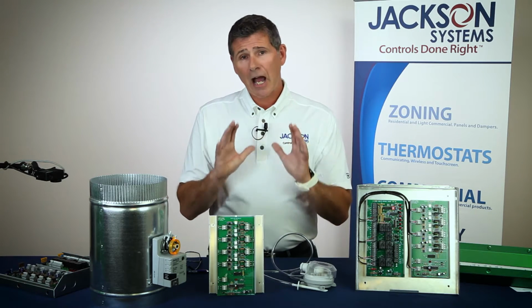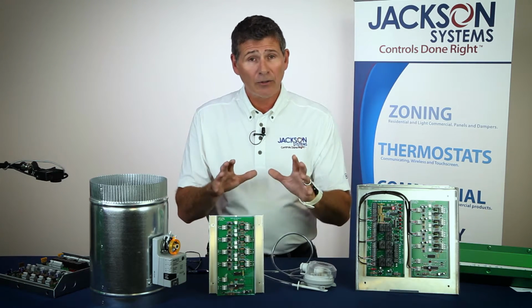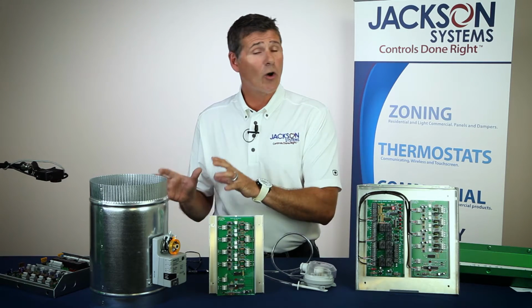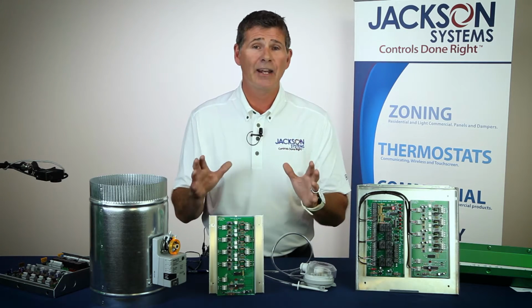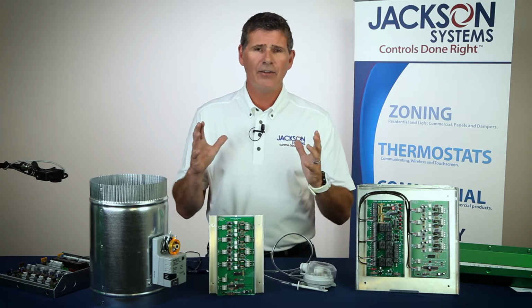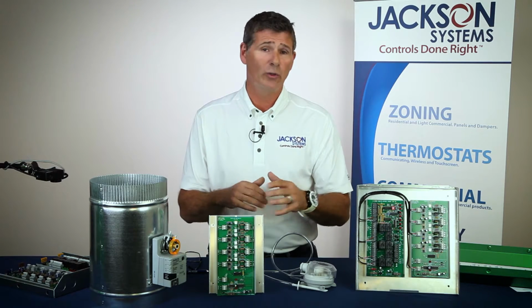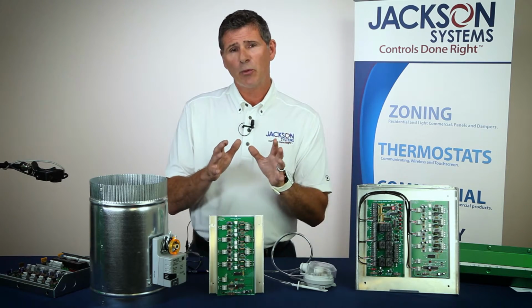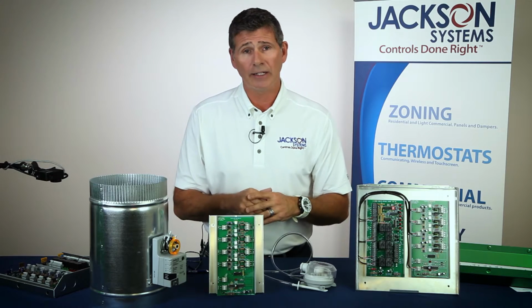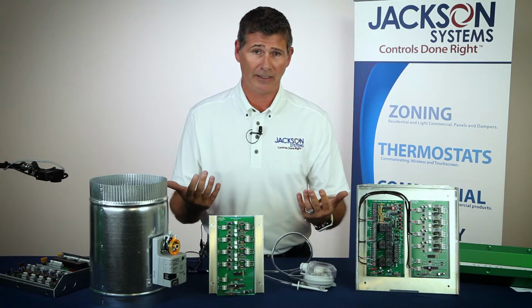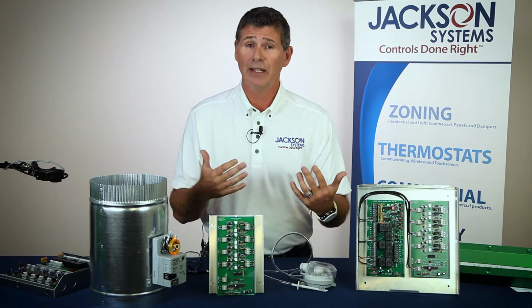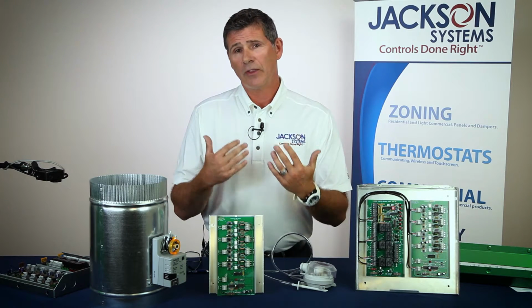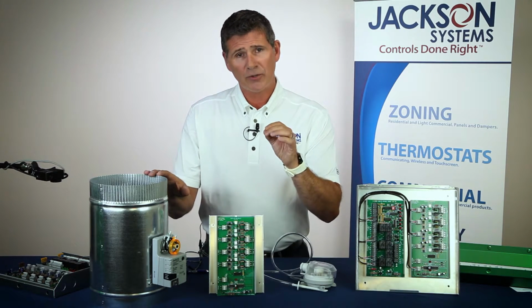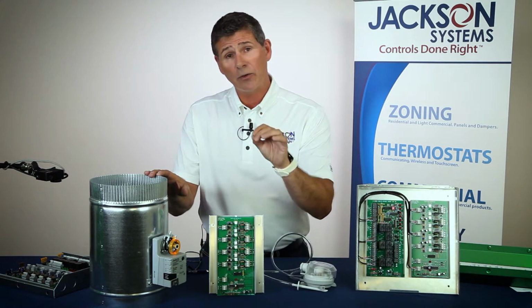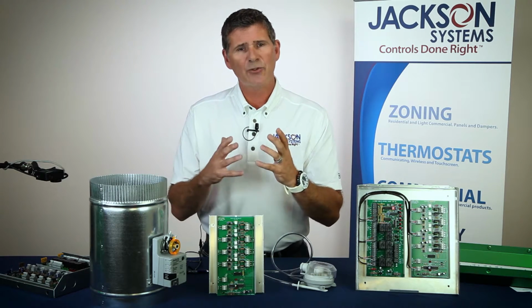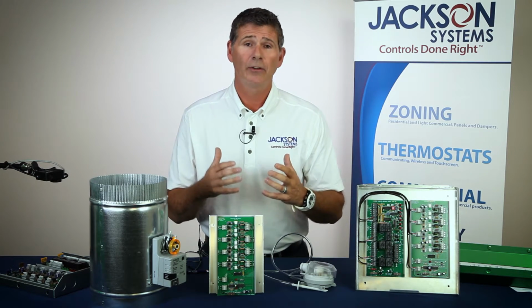Now, this is not going to put enough conditioned air back into those non-calling zones to make any kind of a change dramatically. So you're not going to have any overheating or overcooling issues. So when you think of it this way, if a zone's not currently calling, well, it's in the process of calling, whether it's beginning to cool down or heat up one way or another. So the little bit of static pressure, that conditioned air that's being bled into those non-calling zones, is actually helping to prolong those zones from calling.